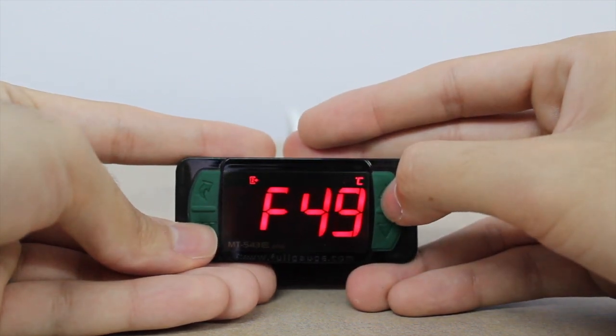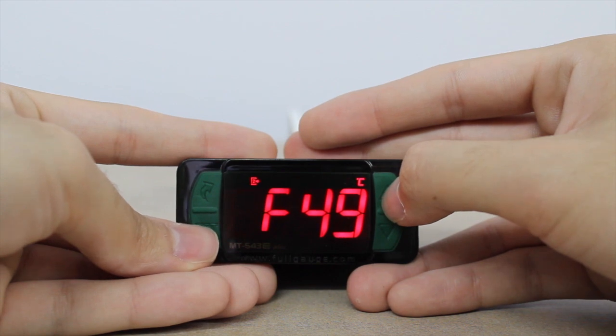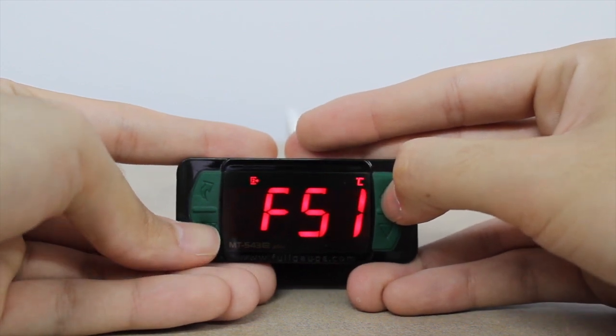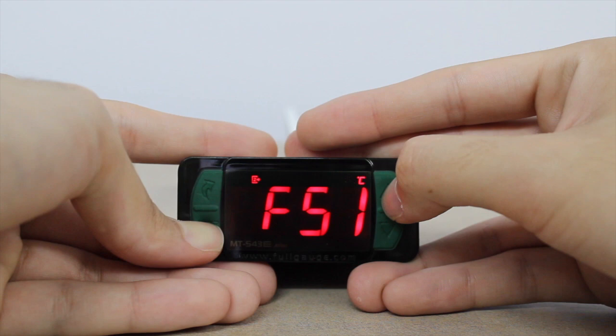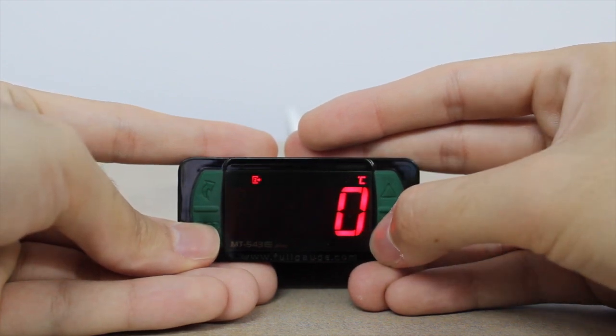And F49 is the time of the second SOAK level. If we set a time of the setting level to zero, it disables the SOAK.